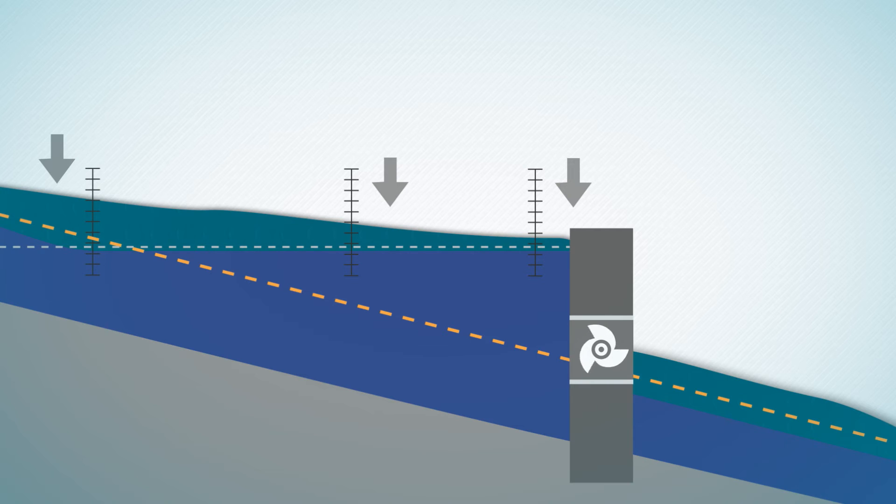Every power plant has a design discharge, which is the maximum amount of water that the turbines can process in order to generate electricity. If this amount of water is surpassed, weirs must be opened in order to manage the additional discharge from the impoundment area.